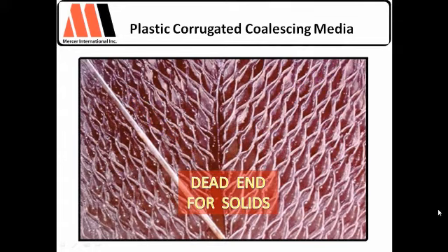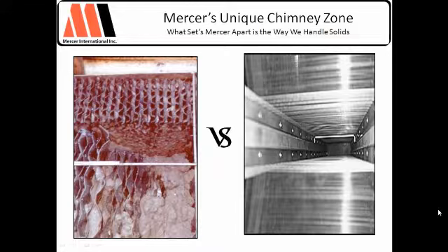Okay, and as we go on, we'll see the difference between a herringbone design with and without an area for solids. Here, two bundles together, and what's happening is the weight of the solids that have built up eventually overtakes and collapses the packs. The packs are not inexpensive, and as the solids build up, they sit, and finally you'll see what's happening here.